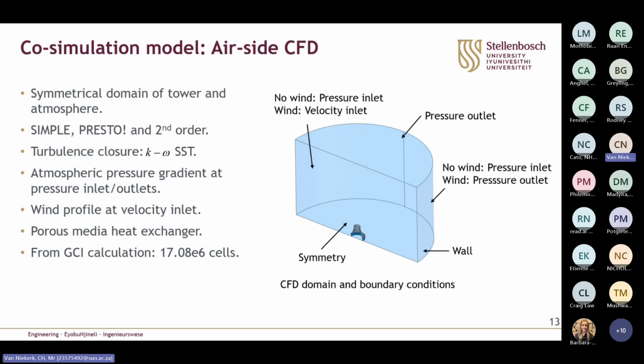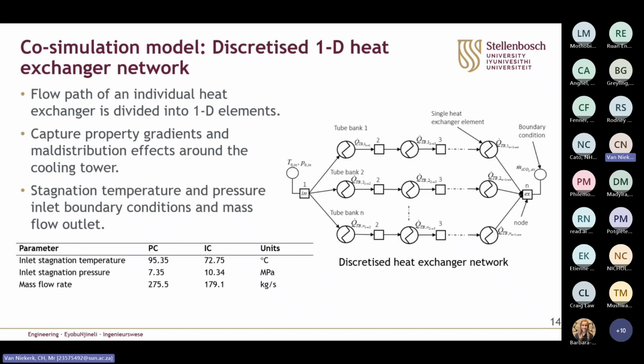And then finally, to ensure that our model is accurate, we completed a grid convergence index calculation and ended up choosing a 17.08 million cell mesh. For the SCO2 side process model in Flownex, which consists of the discretized heat exchanger network, this effectively just takes the flow path of an individual heat exchanger and divides it into multiple 1D heat exchanger elements with a defined area and length.